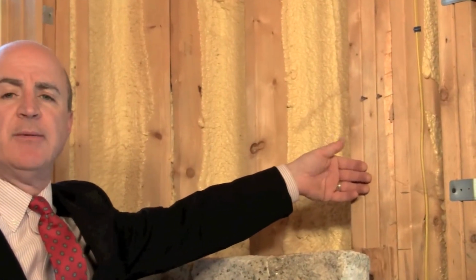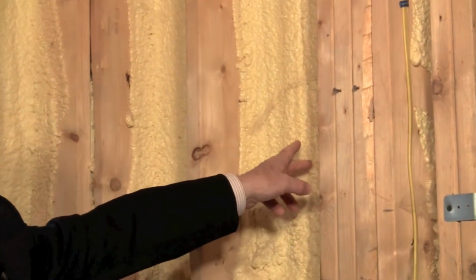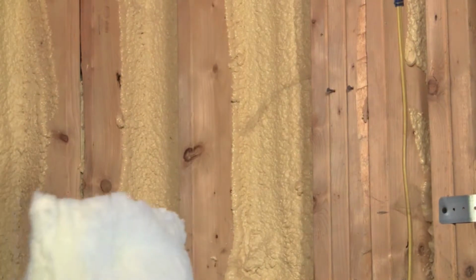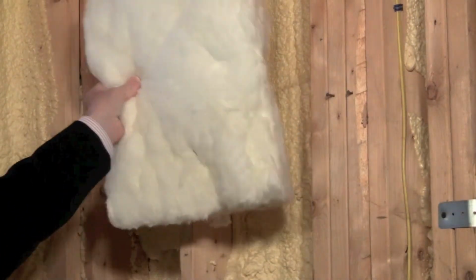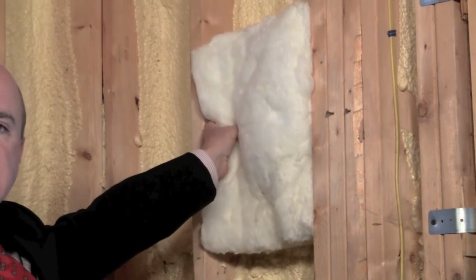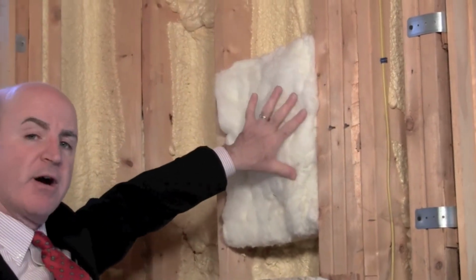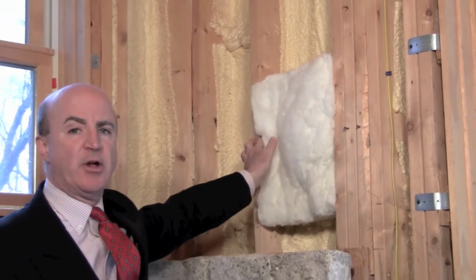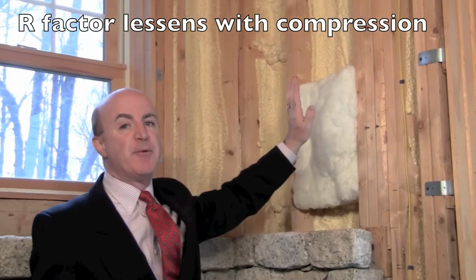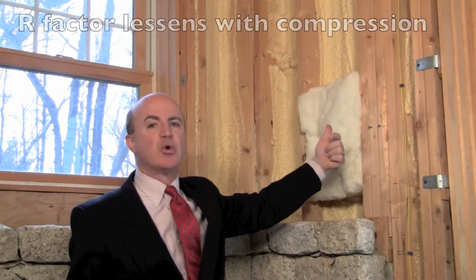There are a couple of methods of installation for foam insulation. You can either fill the entire bay with foam, and then you would cut off the excess with a saw, or you can install 1 inch or so of the foam, let that set up, and then install your typical insulation. In this case, a R7 for the foam, an R13 makes for an R20 envelope. And remember, your vapor barriers always go on the inside or toward the heated space and not away.